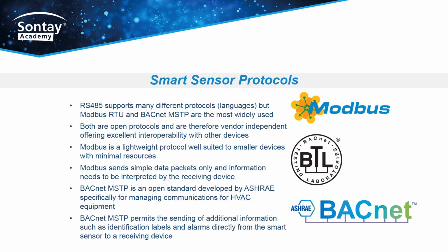Modbus was invented in the 1970s by the Modicon Corporation as a means of exchanging data between process control systems. The limitations of technology at the time required it to be a very lightweight protocol, operating at a low baud rate. It was never developed as an open protocol, but has emerged as such, with the owners putting no restrictions on Modbus. But the lack of a standard and the hex coding system used can make it tricky to work with. Because of its simplicity, it has been integrated into smaller and smaller devices and has a reputation for reliability.